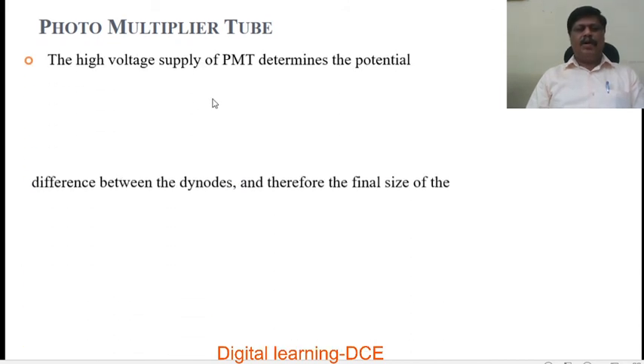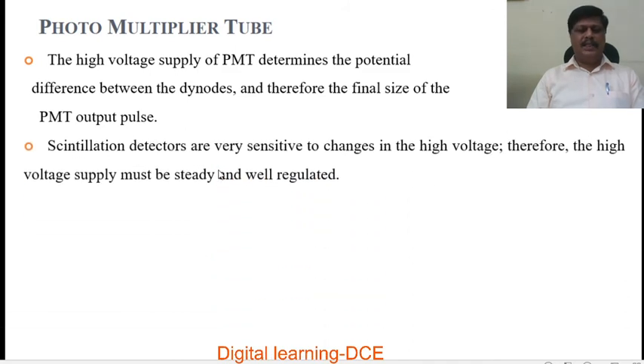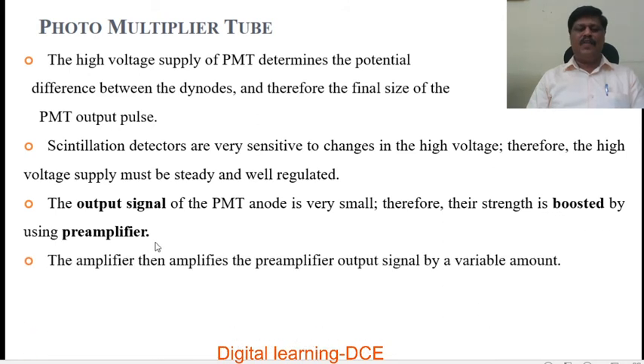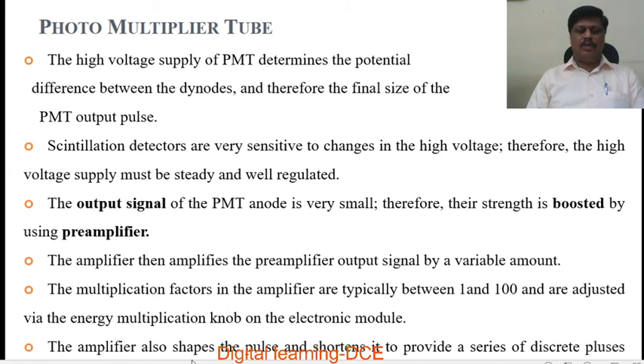The high voltage supply of the photomultiplier tube determines the potential difference between the dynodes and therefore the final size of the PMT output pulse. Scintillation detectors are very sensitive to changes in high voltage, so the high voltage supply must be steady and well regulated. The output signal of the PMT anode is very small, so its strength is boosted by using a pre-amplifier. The amplifier then amplifies the pre-amplifier output signal by a variable amount, typically between 1 and 100, adjusted via the energy multiplication knob on the electronic module. The amplifier also shapes the pulse and shortens it to provide a series of discrete pulses.